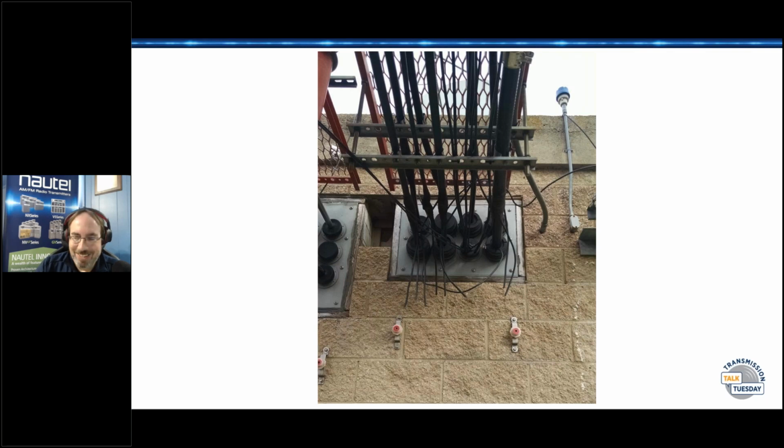Oh, more than one site that I have visited, the mice have greeted me, and it's just a regular thing. Not even wintertime. One of the things that I do toward the winter is I will actually take the cover off the electrical panel to see how many mice are living in there and how close to a fire that site is. And that's one of those comments.